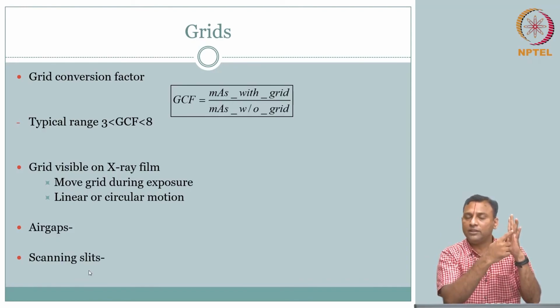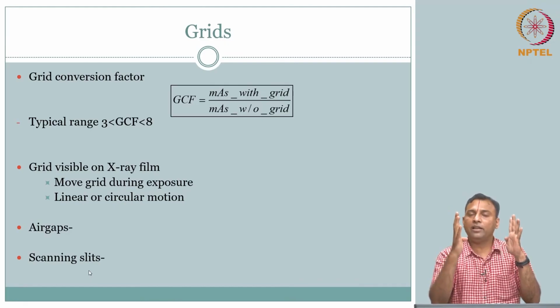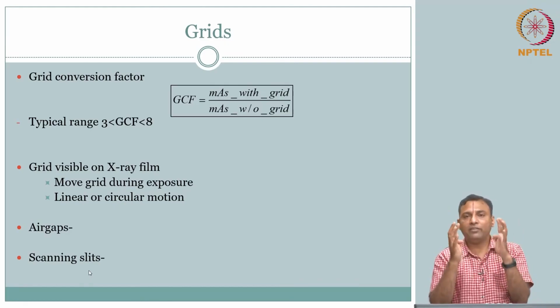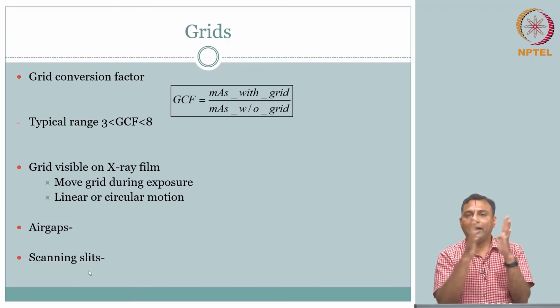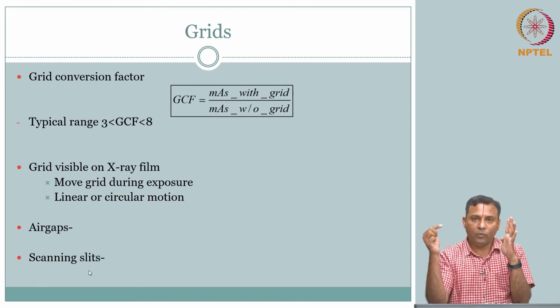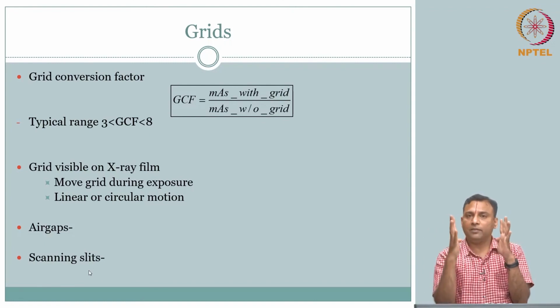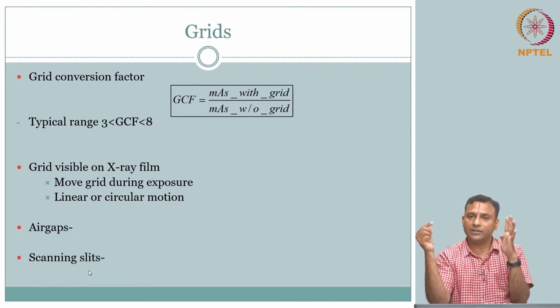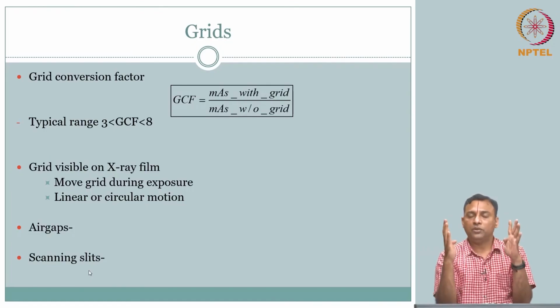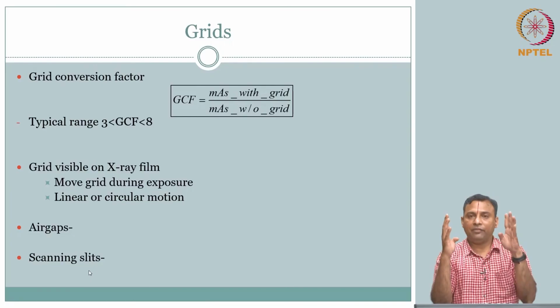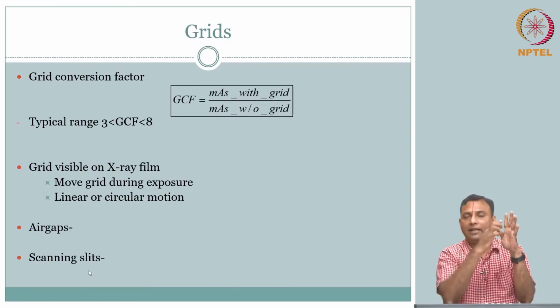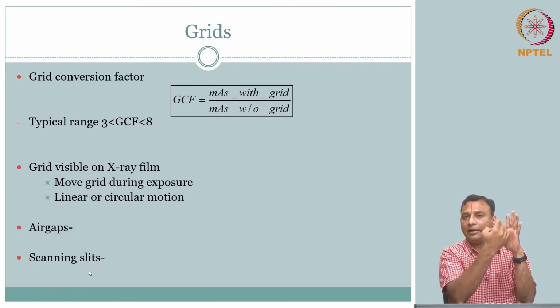Instead, what we can do is have the slit also at the beginning. That way you don't even dose the patient where the grid is. So you align these two perfectly. That way only through the transparent locations in between the slits is the signal going through. Every other angle, even here, it is arrested, and therefore whatever comes out of Compton scattering, you can manipulate here and it can get arrested.